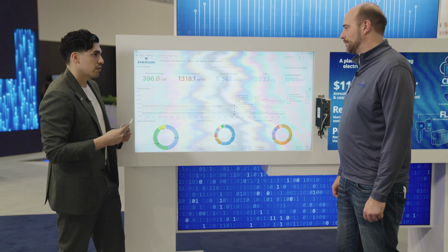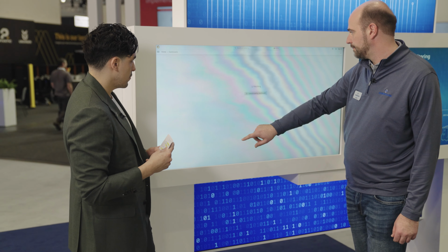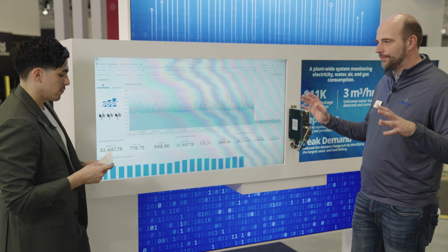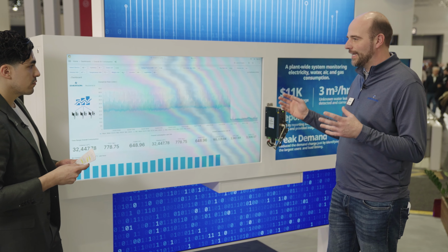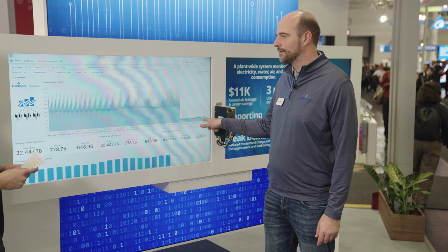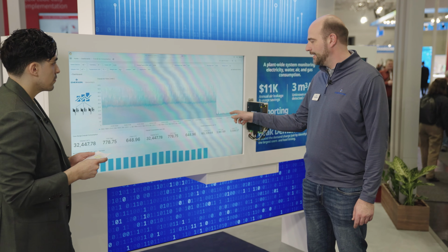What are the main findings that you would really look for when installing a compressed air manager? So when I really look at the compressed air manager, let me switch to another dashboard here, for example. So in Laatzen, we also have a compressed air manager which has a lot of endpoints. And we always see here the baseline. We always capture the baseline. That's our point to start with, because that is leakage normally.